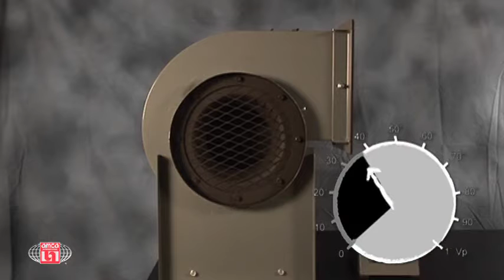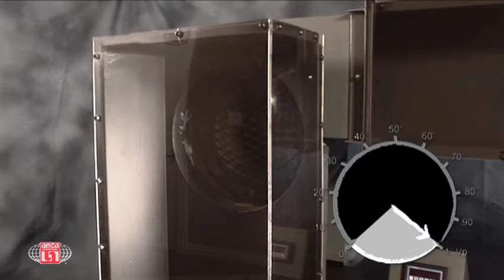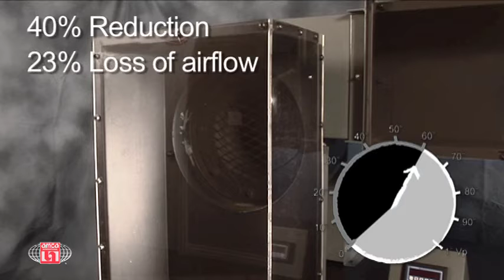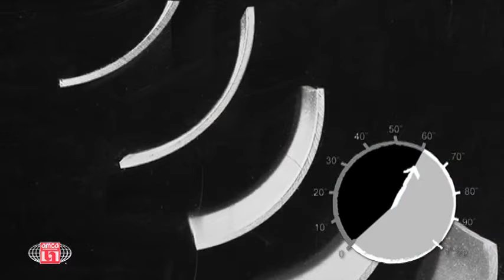Let's assume we use an open inlet as a benchmark, with the inlet velocity set to 1 inch of water velocity pressure. If we affix a poorly designed right angle inlet box directly to the inlet side of the fan, our velocity pressure is reduced to just 0.6 of an inch water, a 40% reduction, which equates to a 23% loss of airflow. If we improve the design by adding turning vanes to the inlet box, we improve the velocity pressure to 3/4 of an inch water, but that's still a 13% loss of airflow.